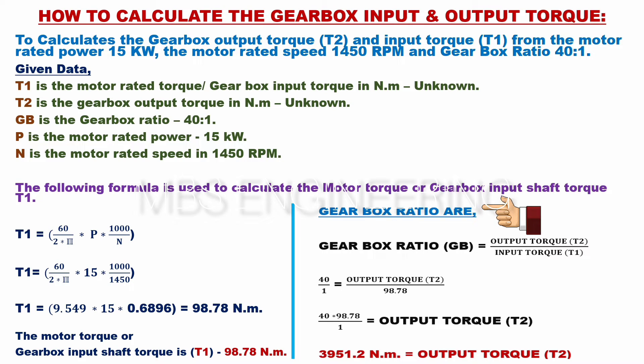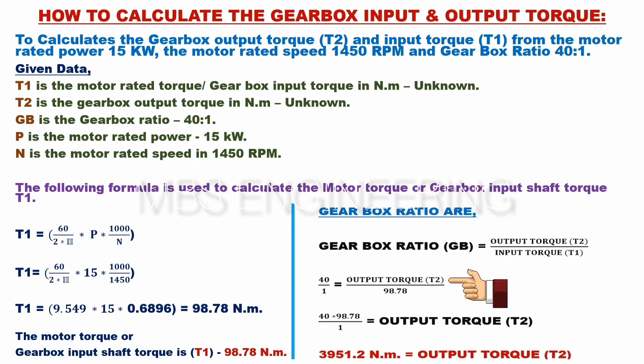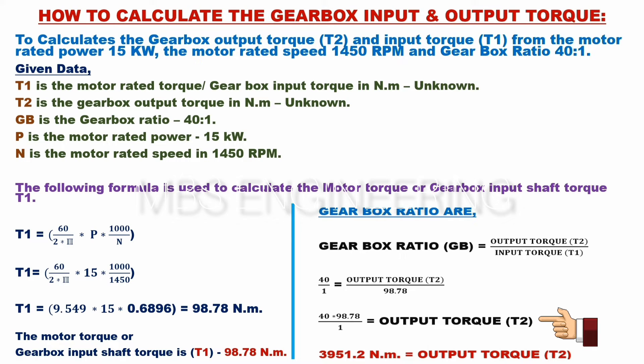Using the gearbox ratio formula: Gearbox ratio GB equals output torque T2 divided by input torque T1. Applying the given data: 40/1 = T2 ÷ 98.78. Therefore, output torque T2 = 40 × 98.78 ÷ 1. The gearbox output torque T2 is 3951.2 newton meters.